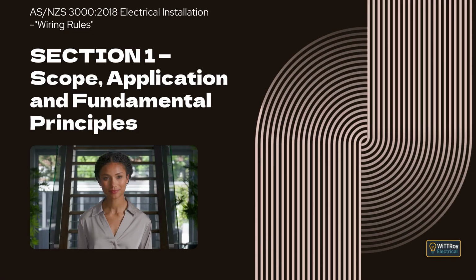Clause 1.5.6 introduces extra protection by the use of RCD devices. RCDs are not allowed to be the only method of basic protection, but they are very useful as extra protection on top of insulation and barriers. Clause 1.5.6.1 says that an RCD can support basic protection, but it cannot replace the normal basic protection such as insulation. It is simply an extra safety layer.